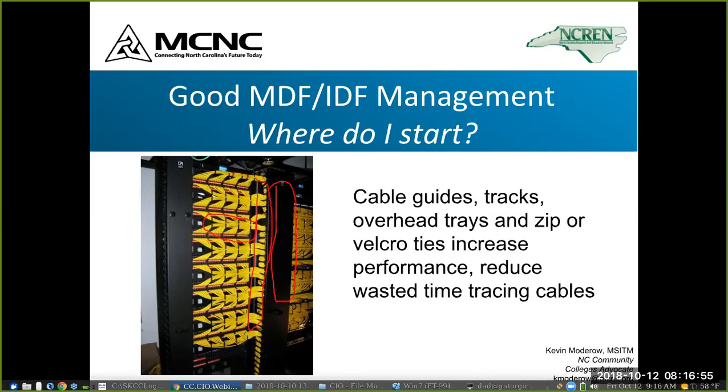In each of these cases, there are not excessive twists or bends in the cable. There isn't any color coding, but there is plenty of room for labeling. And so this is an example of using the best of the best. Also, Velcro ties can keep cables from dangling, getting tripped over, and things like that. So this is an example of best practices here.